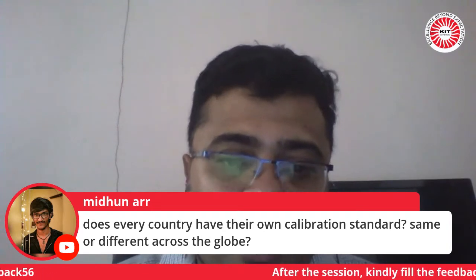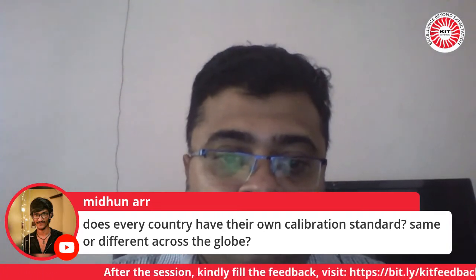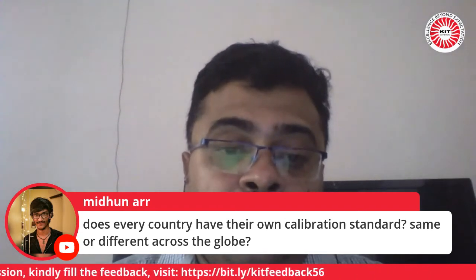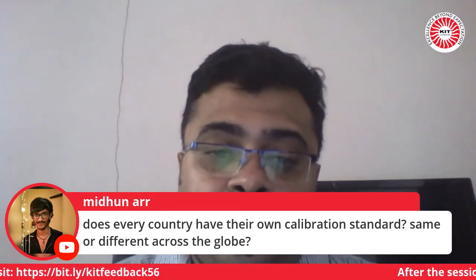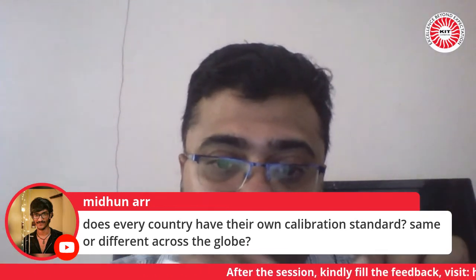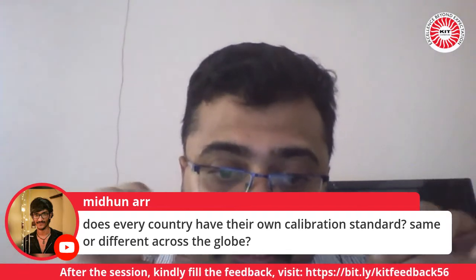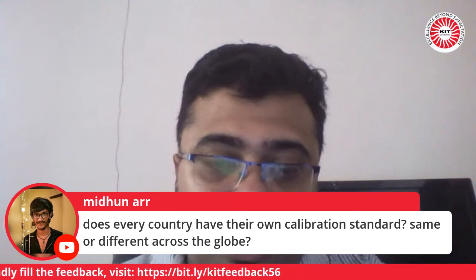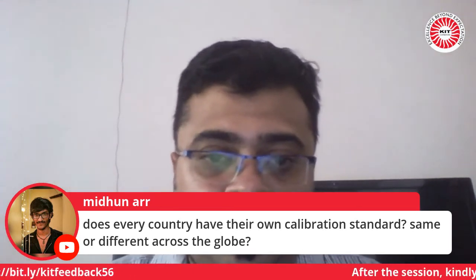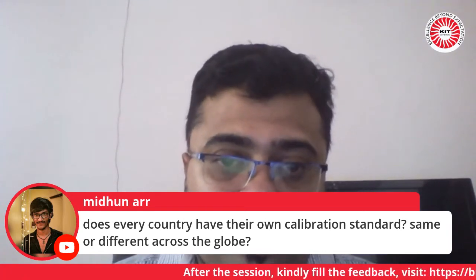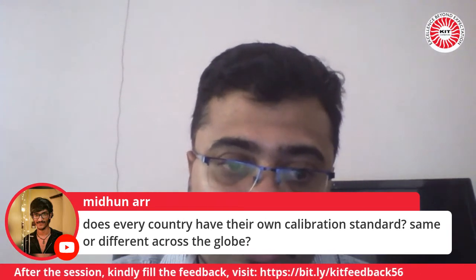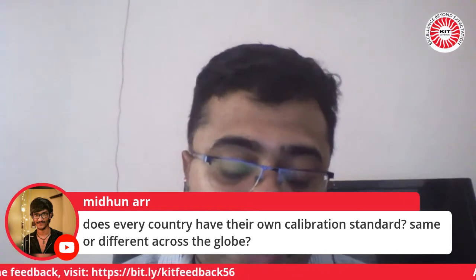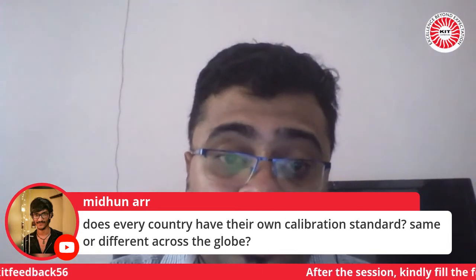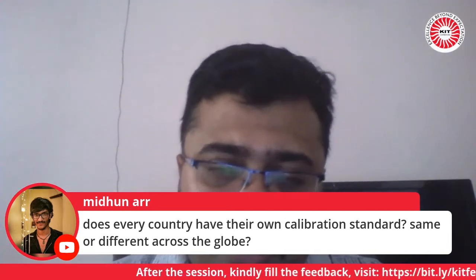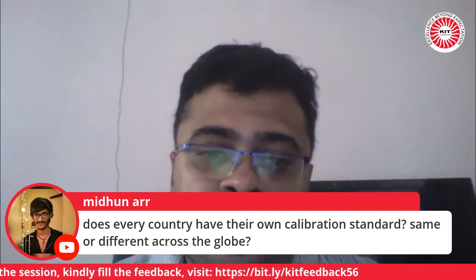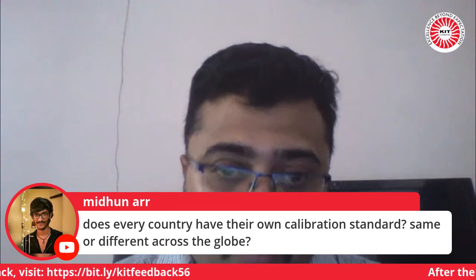Does every country have its own calibration standard? Yes, every country has its own certification standards, connected with calibration standards in different groups. For example, Australia has its own certification standard. Say I pass CE marking or CDSCO marking for India, and I want to sell my equipment to Australia. If I take it there, they will say I need Australian standard certification to sell in their country, with some changes in parameters, for example declaring 80 cmH2O as the safety pressure relief valve standard for their particular ventilator standard.